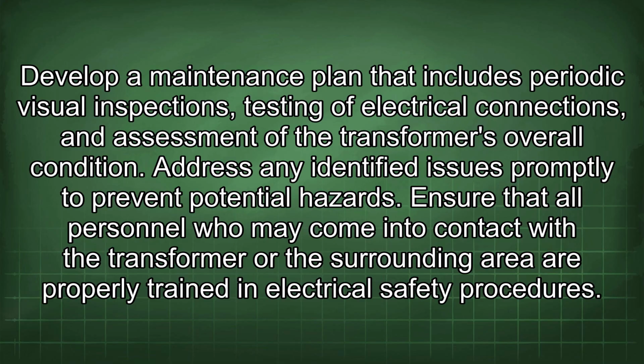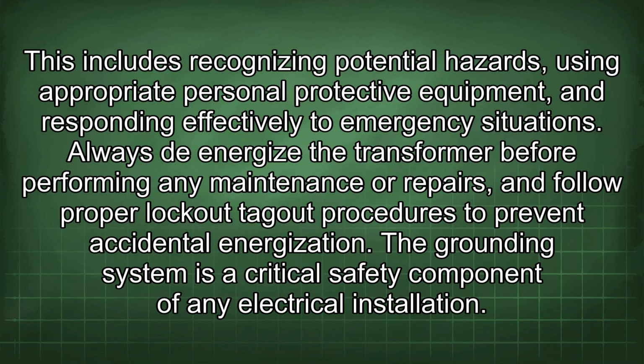Ensure that all personnel who may come into contact with the transformer or the surrounding area are properly trained in electrical safety procedures. This includes recognizing potential hazards, using appropriate personal protective equipment, and responding effectively to emergency situations. Always de-energize the transformer before performing any maintenance or repairs, and follow proper lockout-tagout procedures to prevent accidental energization.